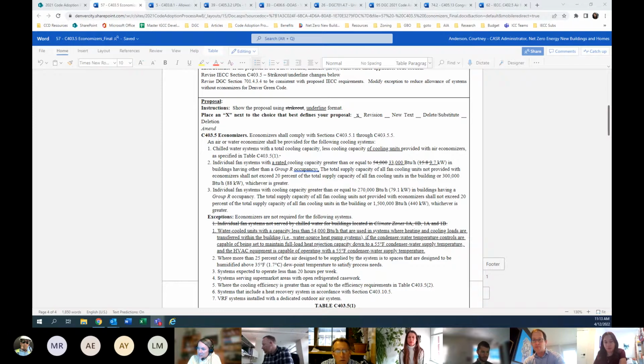So is the intent to apply this to only package systems? Because if I compare a 3-ton rooftop unit with an economizer, the 3-ton split system is more energy efficient because of the fan energy, not because of the cooling efficiency. So there would not be savings in requiring someone to go to a rooftop unit with an economizer at this level. I can't even really justify it at 4.5 tons.